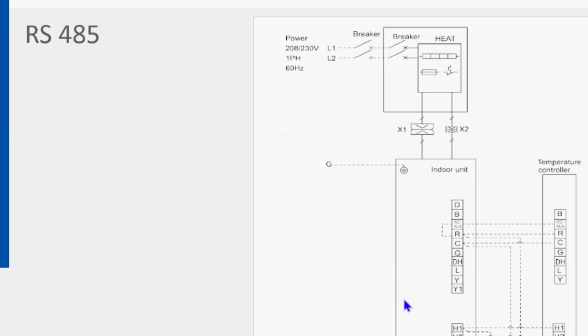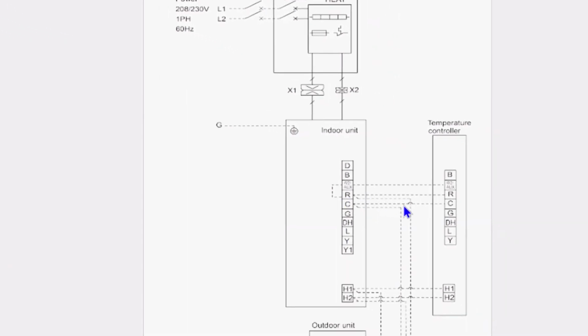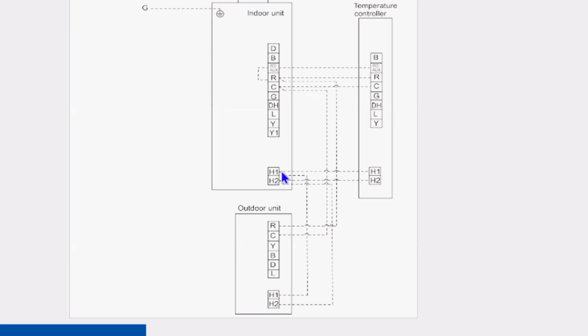So as far as the RS-485, it's pretty simple as far as the wiring. You do have to run R and C to the controller in here. There's also a W2 auxiliary on the thermostat. I think the diagram is a little deceiving in that they're telling you to run a wire from W2 to auxiliary, and you also have to put a jumper from R to W2. Well, if you think about it at all, that really doesn't make any sense. So if you jump R to W2 either at the controller or the air handler, you're accomplishing the same thing. You don't have to have that wire running across there. And then you've got to have R and C going outside, and then you've got to have your H1 and H2 from the indoor unit to the controller, and you also have to have H1, H2 from the outdoor unit to the indoor unit.